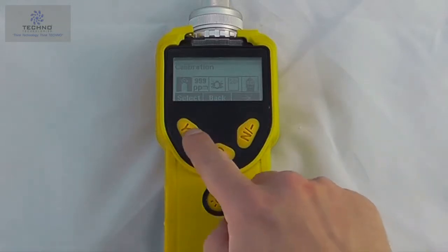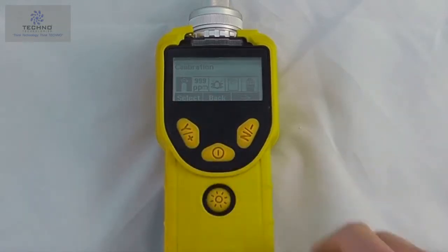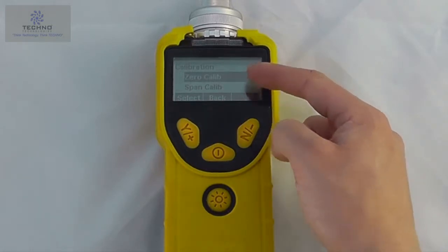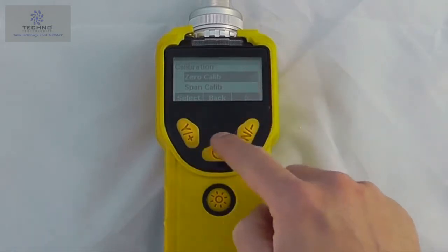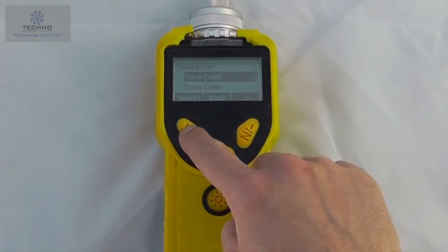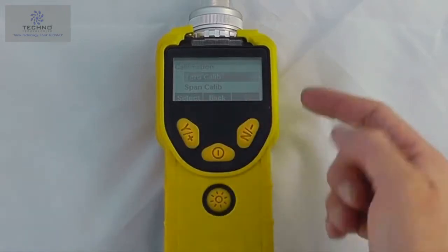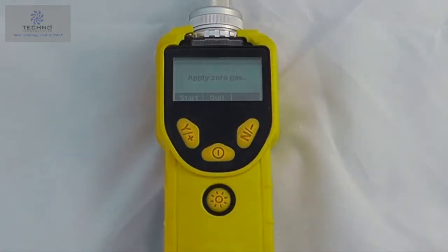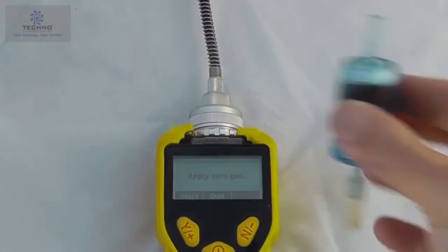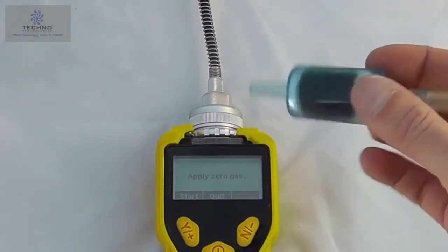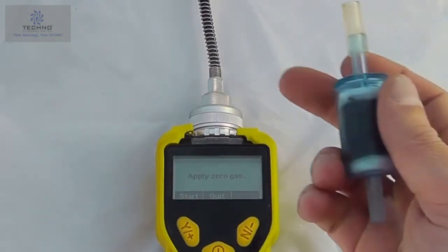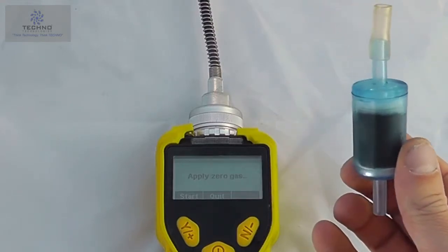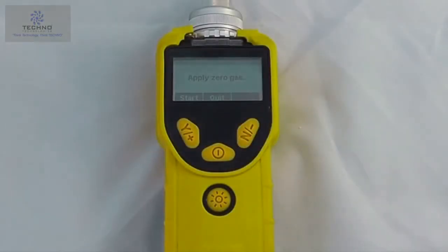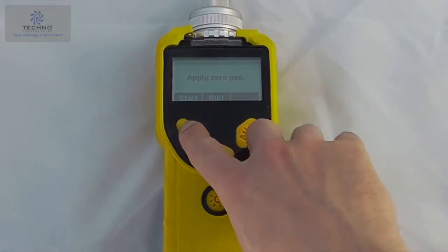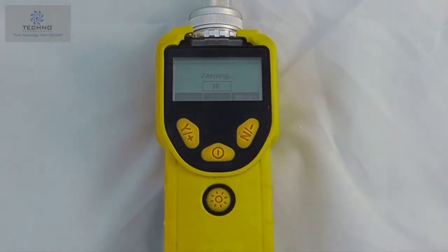So to start the calibration function, select, and we get an option for either a 0 calibration or a span calibration. So to start off with, we'll do a 0, press select. This will then say to apply 0 gas. All the units are supplied with a carbon filter. This will make sure you get a nice clean VOC sample. But in our case, I know I've got nothing in the atmosphere, so we'll press start. And then it will take a 30-second 0.